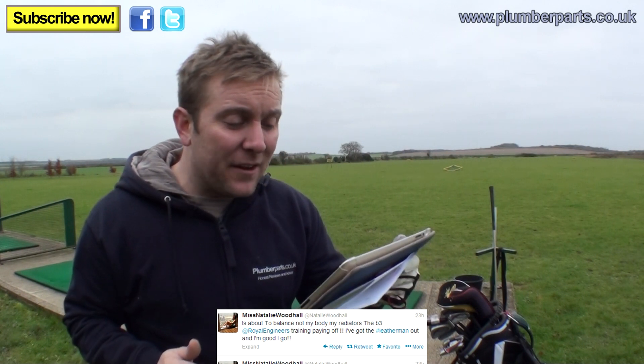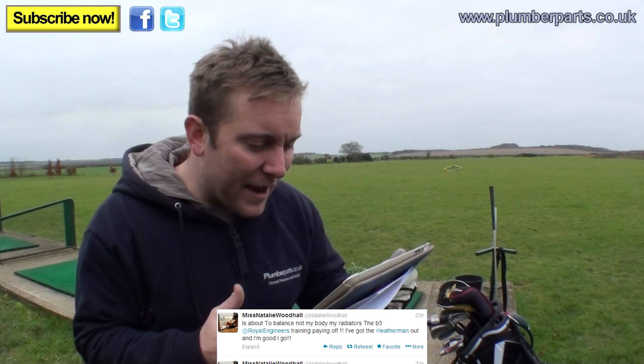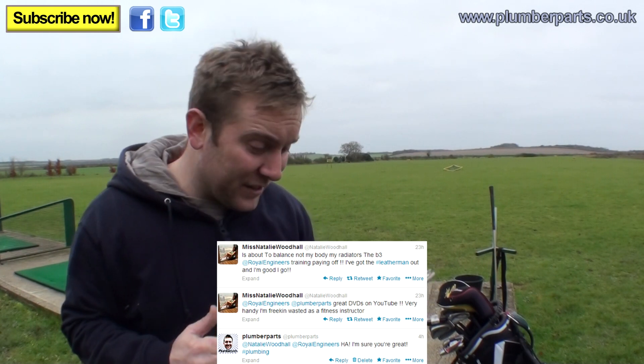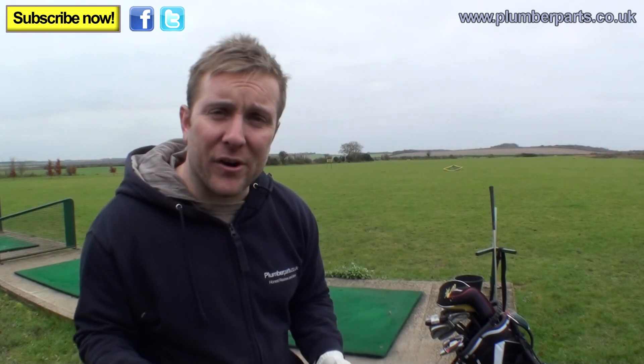On our Twitter account — click the link to follow us — Miss Natalie Woodhall said she's about to balance her radiators. She's got the Leatherman out and she's good to go, referencing our Plumberparts videos on YouTube. She says she's wasted as a fitness instructor. However, it still didn't work — it's still warm at the bottom of the radiator. Before you do a weekend flush-out, turn off all the other radiators in the house but leave that one on, turn your pump speed up to three, make sure there's no air in the radiator, the lock shield's open, and the TRV pin is loose. If it still doesn't get hot, turn off each valve, remove the radiator off the wall, take it outside and flush it out like we showed in our how-to-remove-sludge-from-a-radiator video.